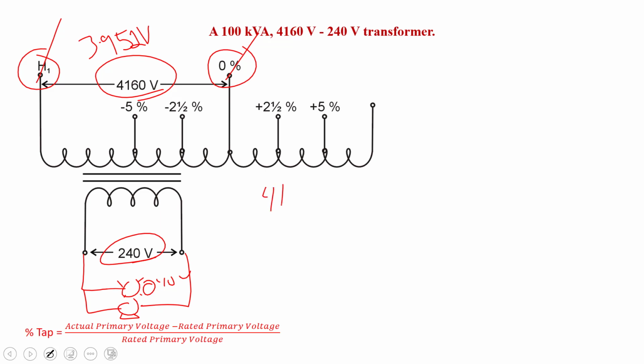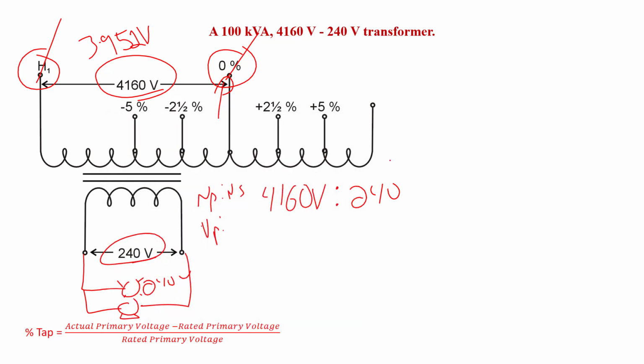Let's just have a look. What's the ratio here of this transformer under normal operations? That is number of turns primary to number of turns secondary. That's how that ratio is established. And we know that's going to be the same as the voltage ratio. So under normal operating conditions at 0% tap with 4160 rated primary voltage, I'm going to go down to 240. So we can establish that ratio of this transformer. Let me just grab my calculator here. 4160 divided by 240 is 17.33 to 1. So 17.33 to 1.